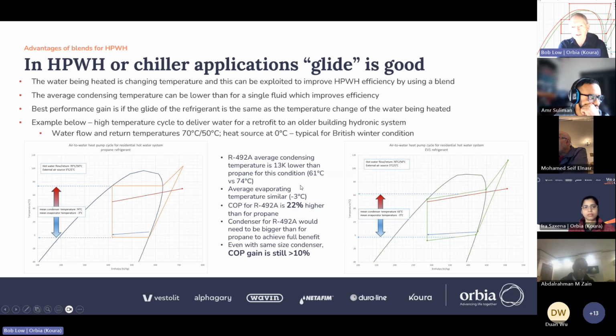492A is a blend of 1132a vinylidene fluoride with R32, R152A and 1234ZE. It's formulated quite deliberately to have temperature glide, and that is because we're looking at chiller applications. And I'm using the term chiller here to mean units that are designed to cool a liquid to produce heat as well as cool a liquid to produce cooling.